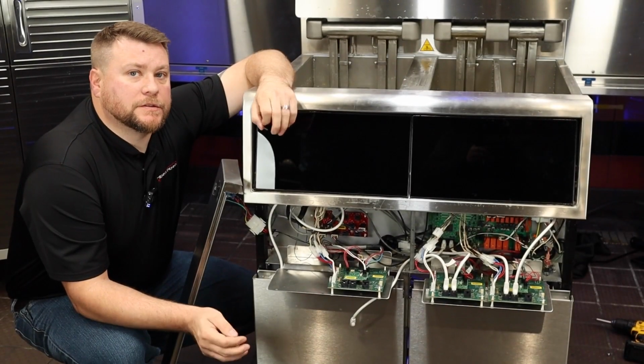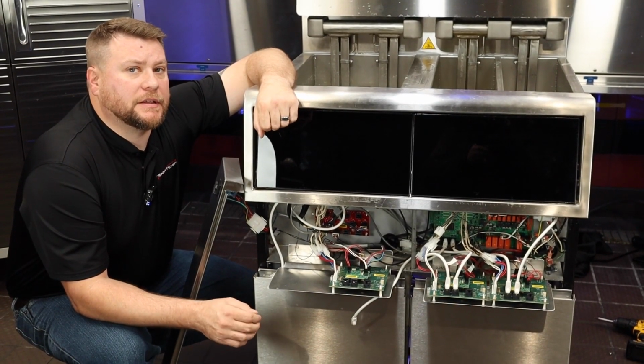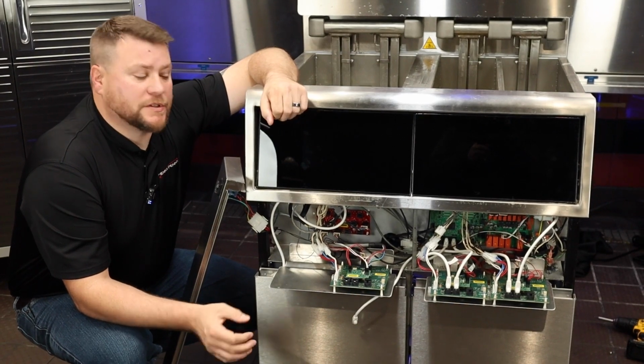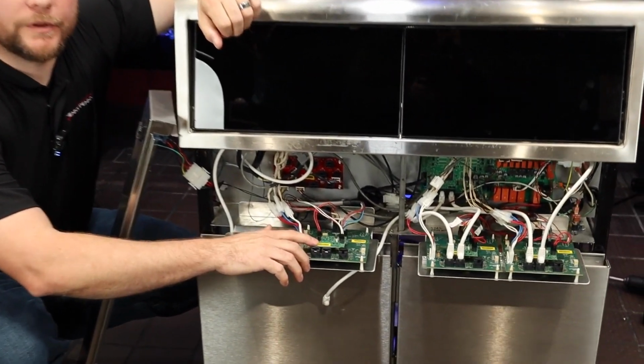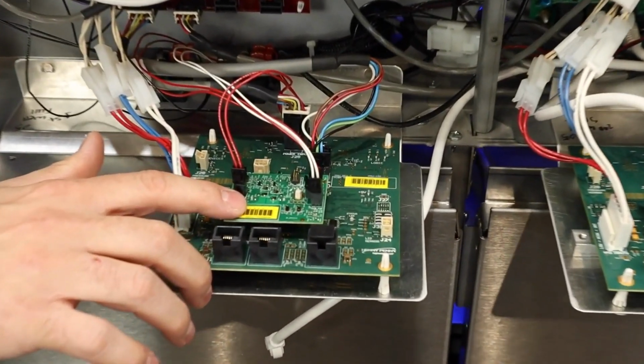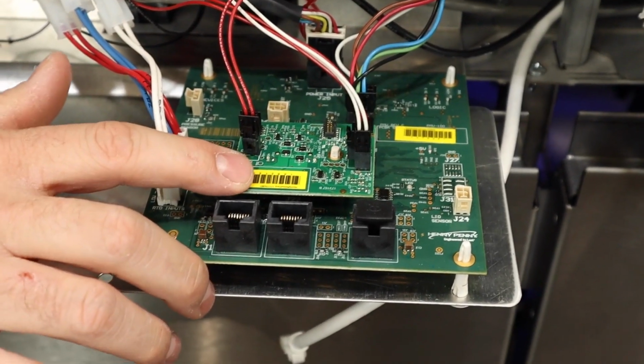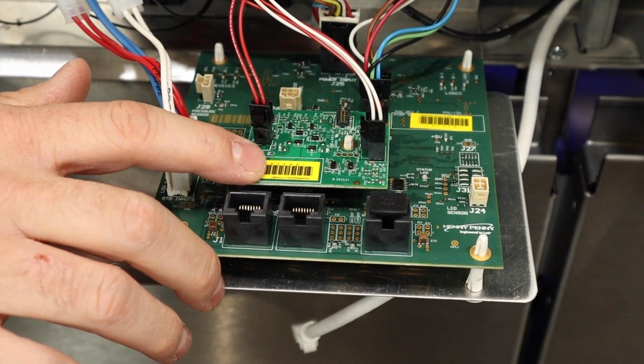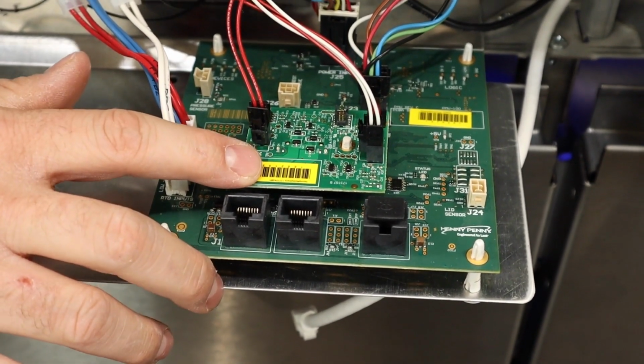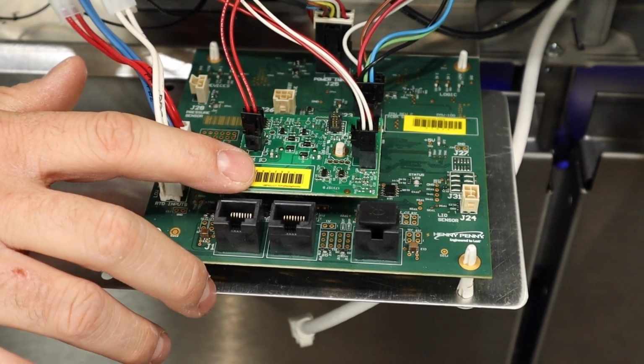A few more error codes in regards to the E10 is going to be an E-10W, which is an internal memory error with our high limit PCB here. So what we could end up doing if we're seeing that E-10W is, of course, first power the unit down and power it back up to see if that error code goes away.